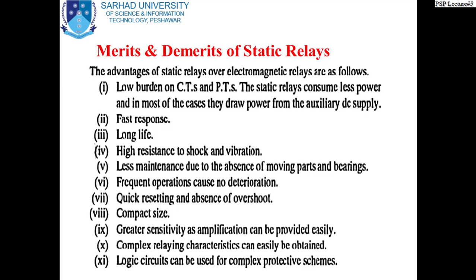Now the fifth point is this: it requires less maintenance because there is no moving part in this particular type of relay. All these things are absent, so it requires less maintenance. Also, the sixth point, frequent operations cause no deterioration, like it occurs in the case of electromagnetic type of relays. The seventh point is quick resetting and absence of overshoot. The eighth point is compact size. The ninth point is greater sensitivity, as amplification can be provided easily. The tenth point is that complex relaying characteristics can easily be obtained. The eleventh point is that logic circuits can be used for complex protective schemes.